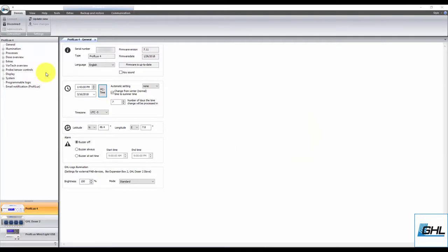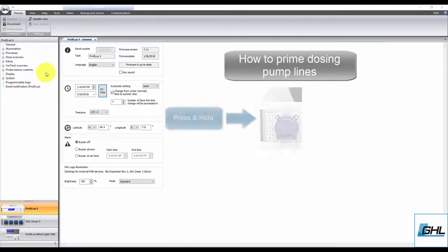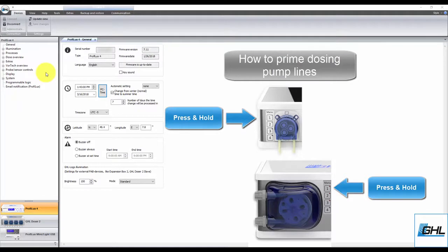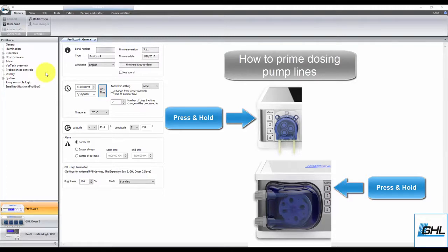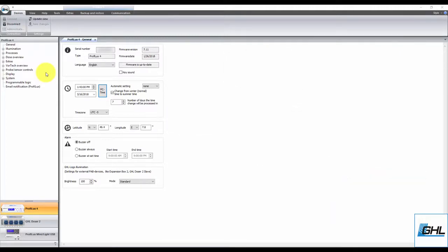Before you get started, make sure you have your dosing lines already installed and primed with fluid. If you don't have the lines primed just yet, you can always prime them by pressing and holding down the manual override button on the dosing pump itself. Press and hold this button until both the in and out dosing lines are filled up with fluid. Once that's done, you can go ahead and begin the calibration process.